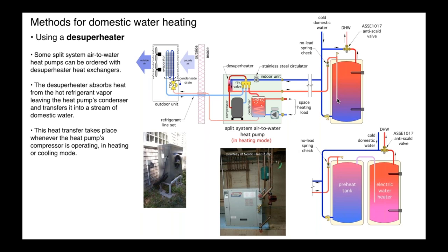Now, during cooling mode operation, this is essentially free domestic water heating because that energy would otherwise be going outside and just dissipated through the outdoor unit. In a geothermal system, same thing, it'd be dissipated into the ground. So in cooling, we're really getting a nice free benefit of domestic water heating. And even in heating mode, we're still getting a benefit here.